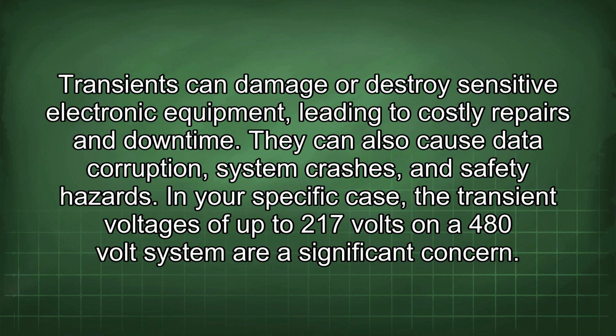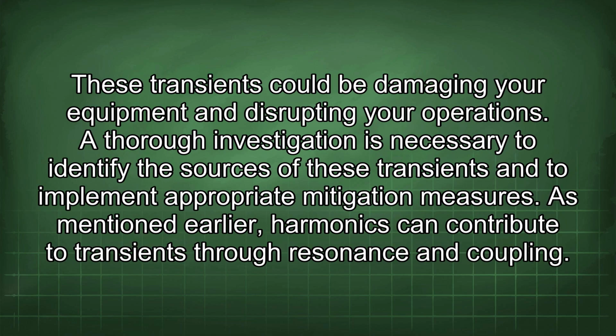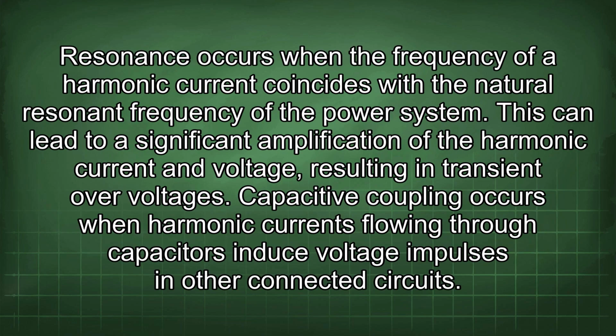In your specific case, the transient voltages of up to 217 volts on a 480 volt system are a significant concern. These transients could be damaging your equipment and disrupting your operations. A thorough investigation is necessary to identify the sources of these transients and to implement appropriate mitigation measures. As mentioned earlier, harmonics can contribute to transients through resonance and coupling. Resonance occurs when the frequency of a harmonic current coincides with the natural resonant frequency of the power system. This can lead to a significant amplification of the harmonic current and voltage, resulting in transient overvoltages.